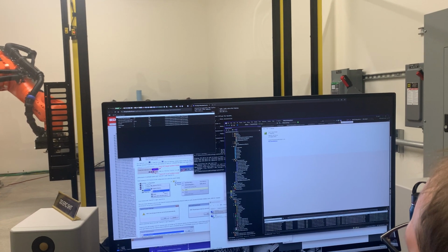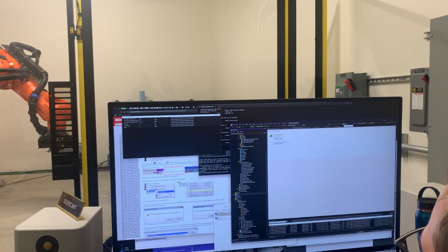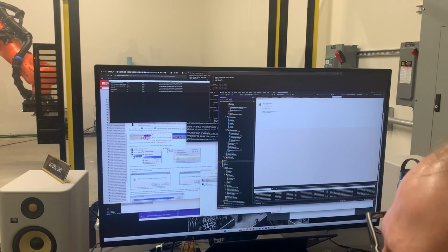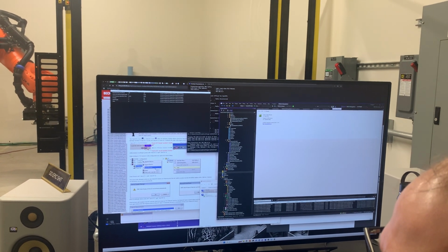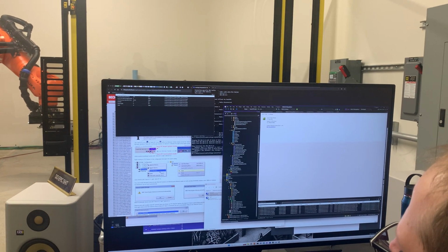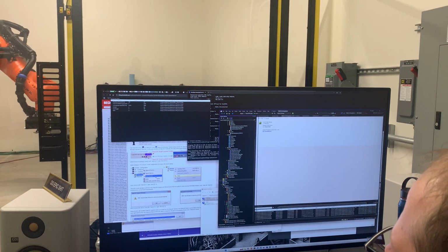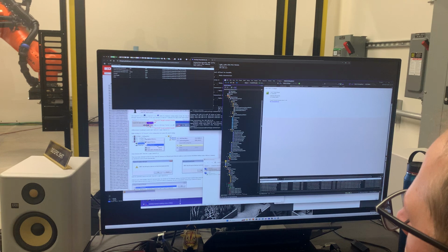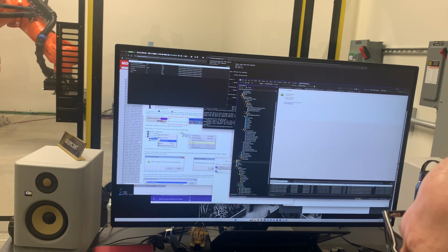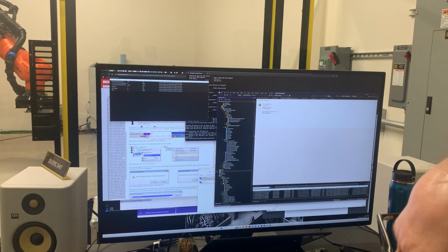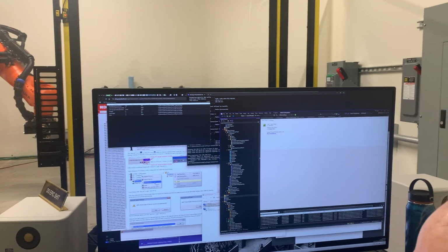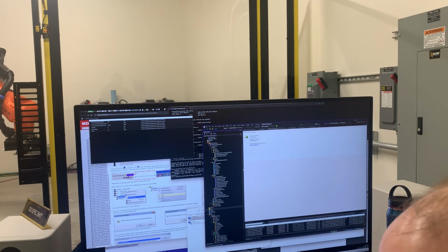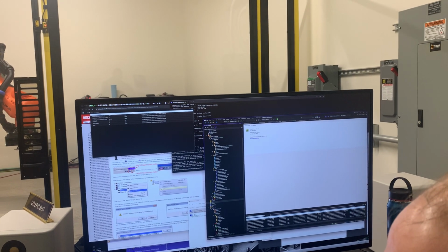That signifies that you've made a hardware change, like to the I/O. I'm not sure how it reacts with the C++ modules. You may have to activate a configuration, but if you're just changing PLC code, whenever you log into the PLC, it'll recognize that your code doesn't match, and it'll prompt you to do a couple of things. Log in.